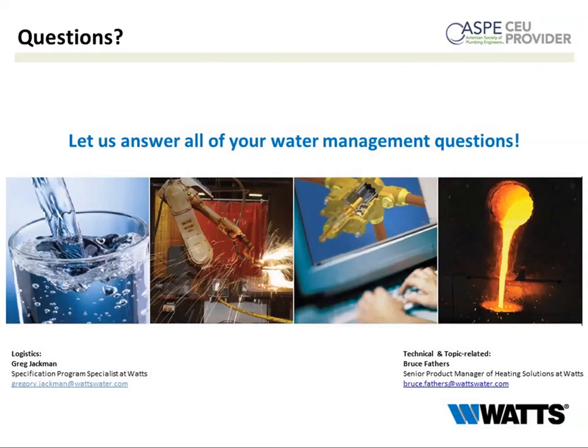Okay. Having the TMV at the point of source further from the POU wouldn't increase the Legionella risk? Well, one of the things is you've got to be able to move the water too. A lot of codes and standards require water to be run continuously. What we're also seeing is that water temperature seems to be a trend, and it'd be interesting to know. I know that's not one of our polling questions, but we're seeing more and more codes and even engineers specifying hotter water at the point of source. So we used to see a lot of 120, 125 from the TMV or the digital TMV.